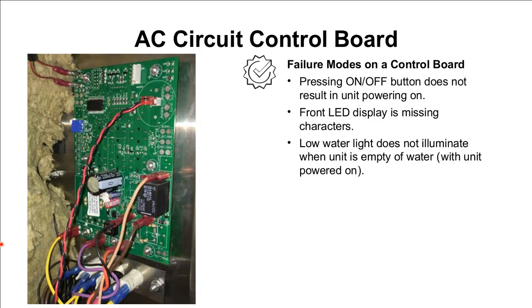Finally, if you're starting your test with the unit empty of water, as soon as you power it on, a low water light should illuminate, and that's constant across the board, autofill or manual fill. If your low water light does not illuminate when the unit powers on, it is a sign that there could be a problem with the control board, so that's where you'd start your troubleshooting.